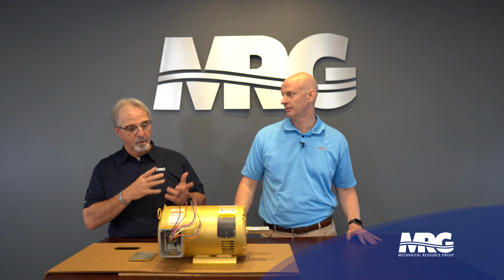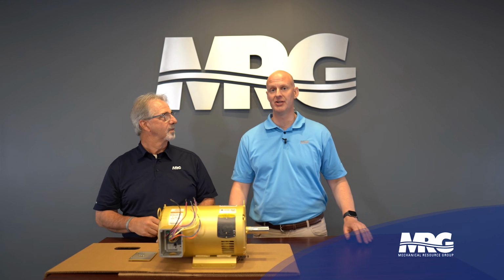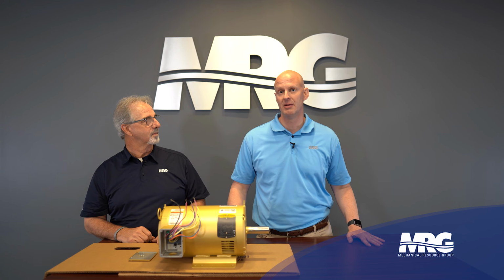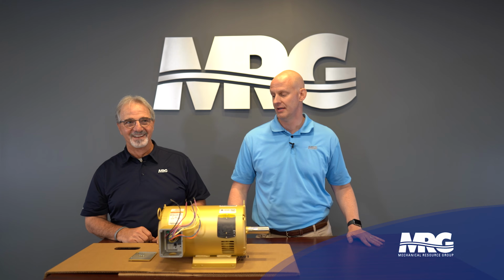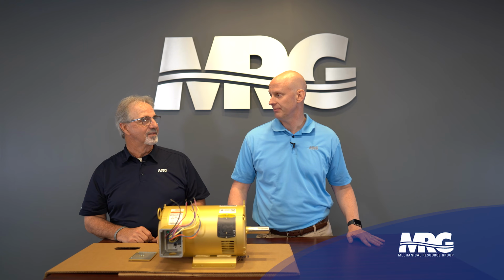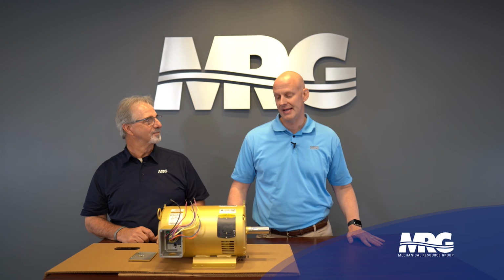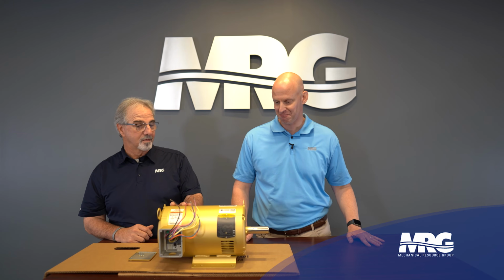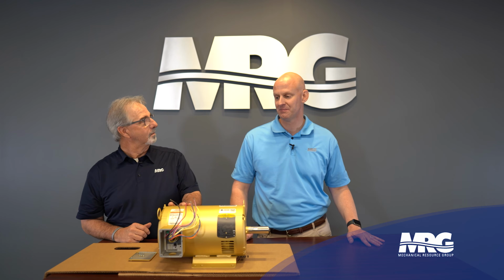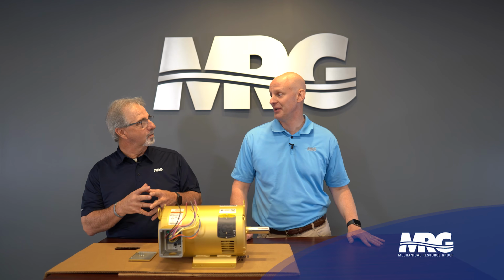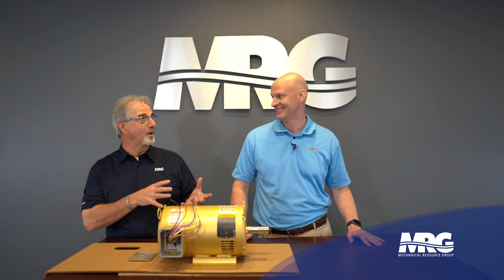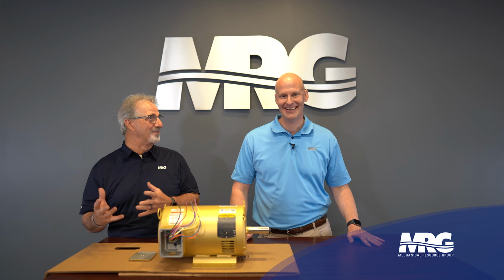Can I tell a story? Yeah, go ahead, tell a story. So I first met Jeff on a job site in the middle of nowhere, Tennessee. I think it was about a 200 horsepower pump motor. It's very large. We had it wired up wrong or something, and it was running really hot, and we couldn't figure it out. We knew Jeff was the local motor expert. Called him out there, and he basically told us we had it wired wrong. And motors are dumb animals. I mean, they respond to how you connect them. Or they don't. Well, no, they're going to respond, and the response can either be good or bad, one of the two.